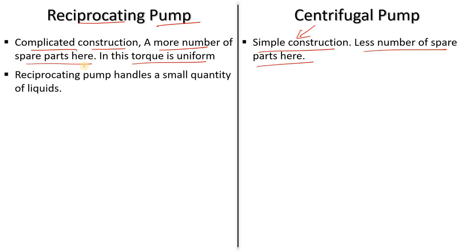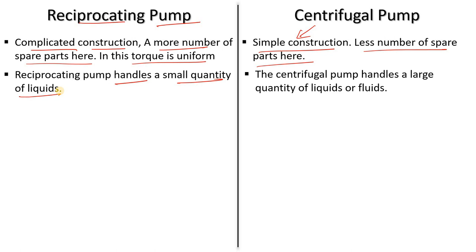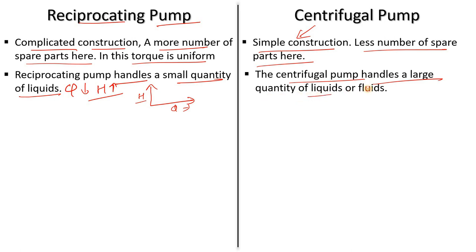The reciprocating pump handles a small quantity of liquid. It is favorable where small flow rate (Q) and high head are required, because compressing the system raises pressure very fast. That's why it is called a high head pump and constant flow pump. The centrifugal pump handles a large quantity of fluid, which is why it is called a high volume pump.